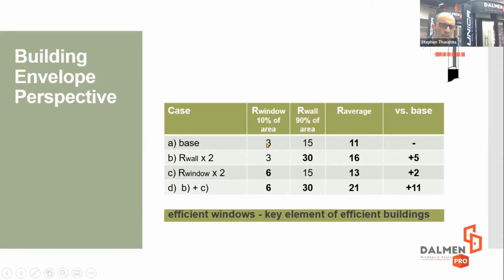You can see that the windows, even though they're a small part of the area, are pulling this number down. So if you say, okay, I'm going to make my wall insulate twice as well—10% of your wall area is still R3, most of your wall area is R30—you go from 11 to 16. You're adding R15 here, but you're only going up R5 overall, because you just made something that's not the weakest link in the chain stronger.